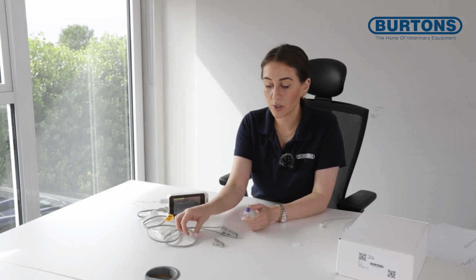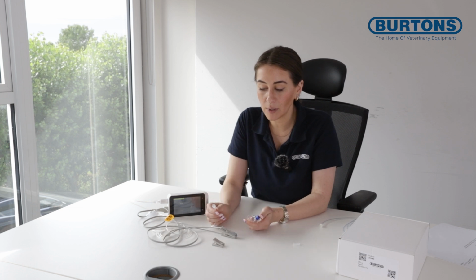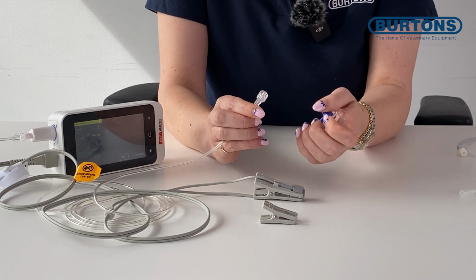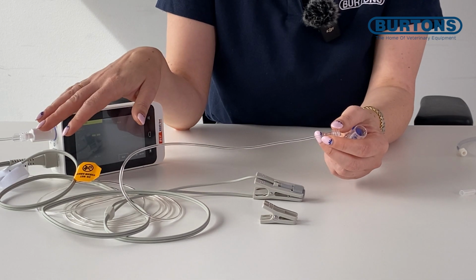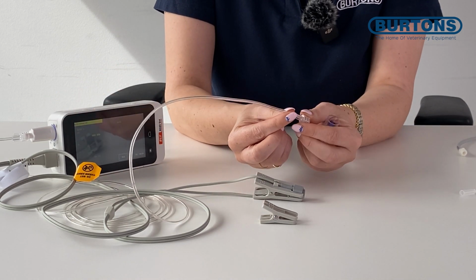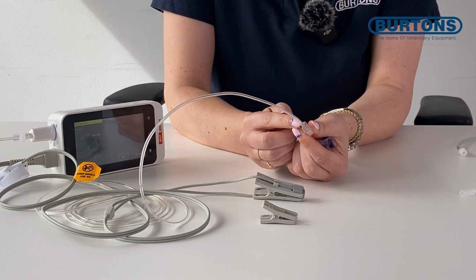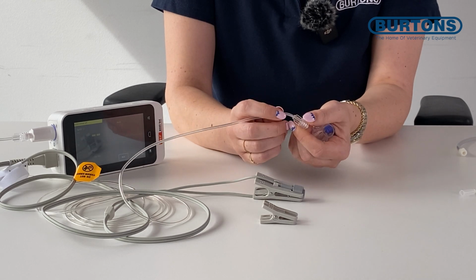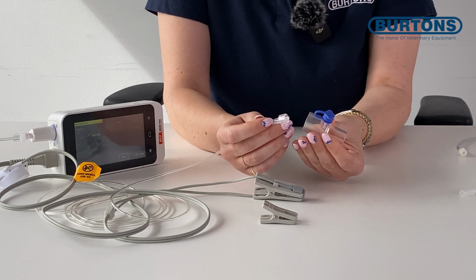In terms of CO2, the main issue that we'll have is what is represented on the screen. So if we have a patient that has a low end tidal CO2, the first thing that we might think of is that we've got a leak somewhere. So leaks can form at any point in the system. Very typically a crack will form in the sample line just here, as over time it starts to wear. The first thing that we think of typically if we have a low end tidal CO2 is that there's a leak in the ET tube cuff.